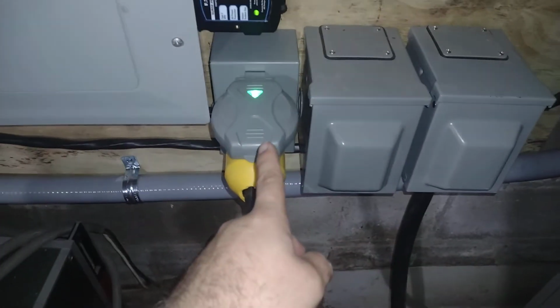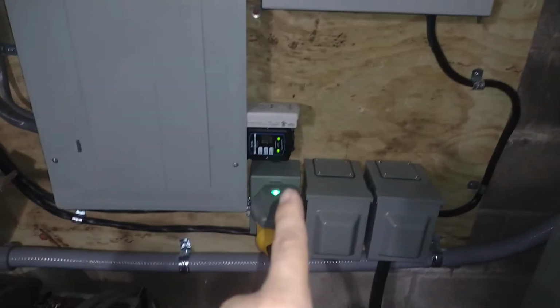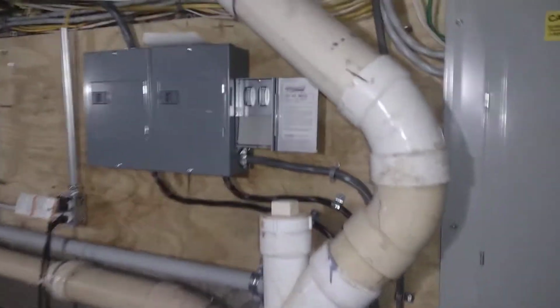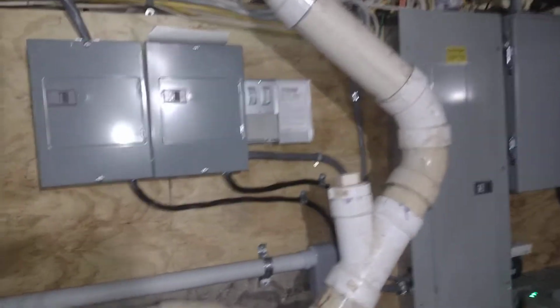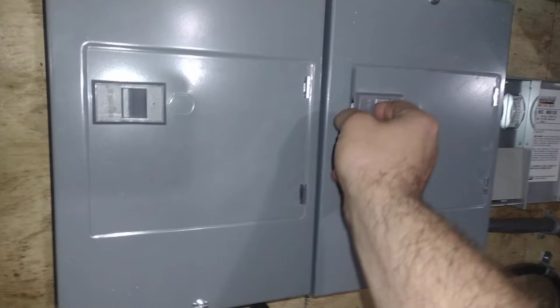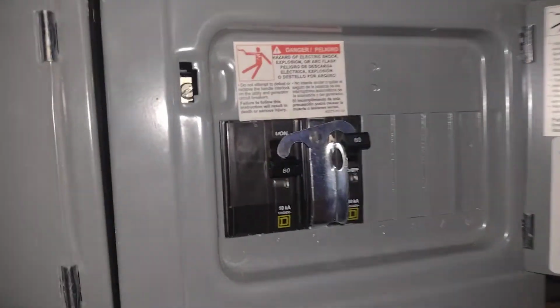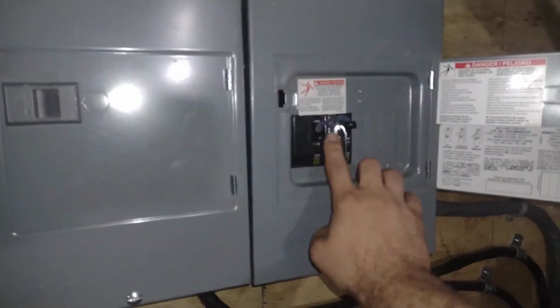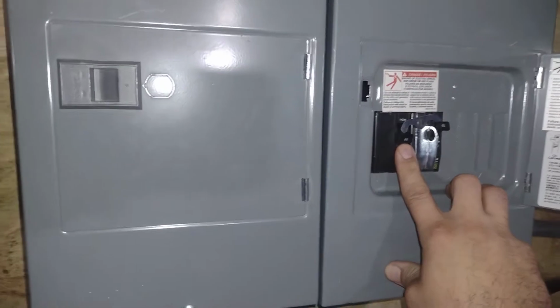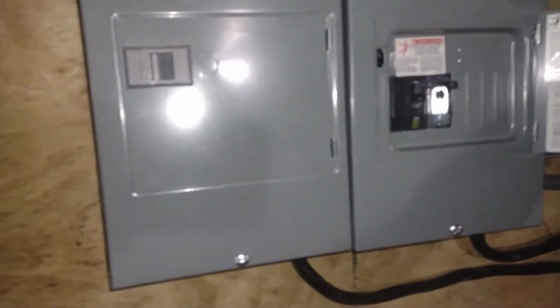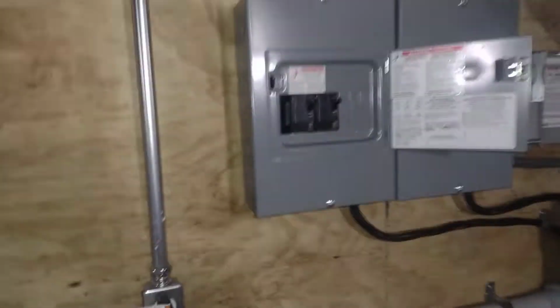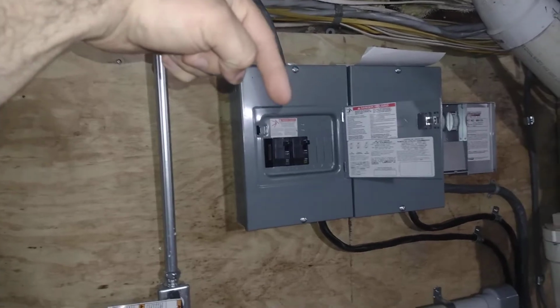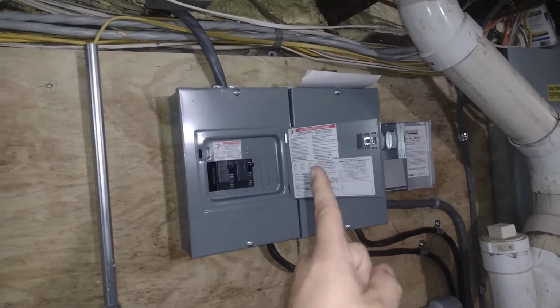So right now, this is going up into the panel. Oh, I'm sorry. This is going up into that panel. And from this panel, we have another interlock. This interlock will pick to either pull power from the solar or from the diesel generator. Obviously it's set on solar right now, but I gotta label this stuff up too. What's this other panel? This other panel is a generator sub panel. So I've got the generator coming in here, then one breaker feeds this, so I can select between solar or diesel.